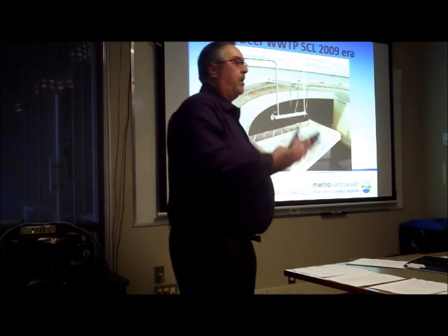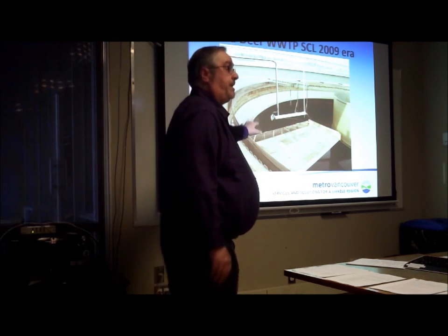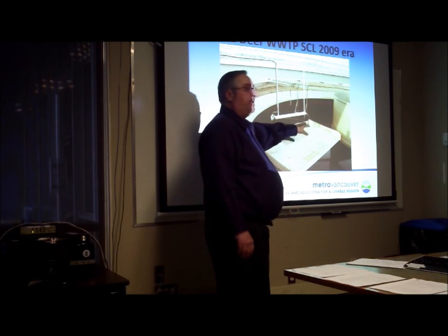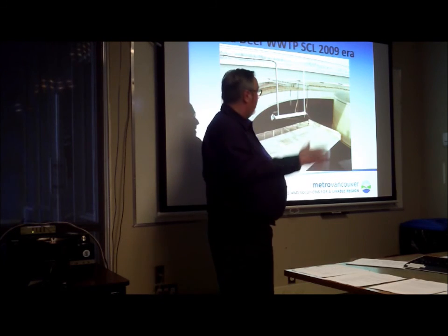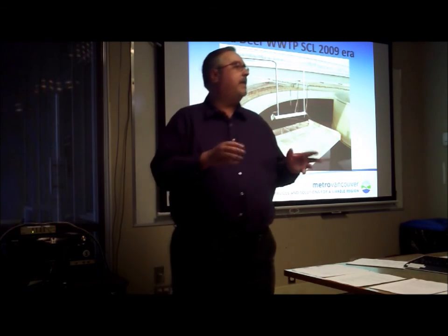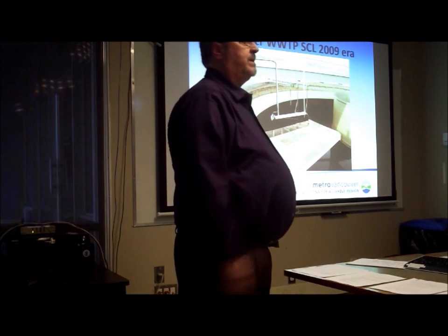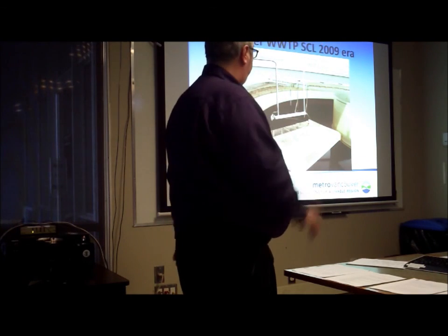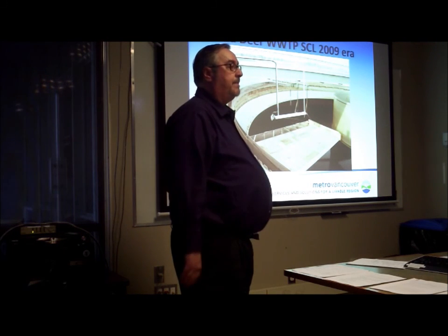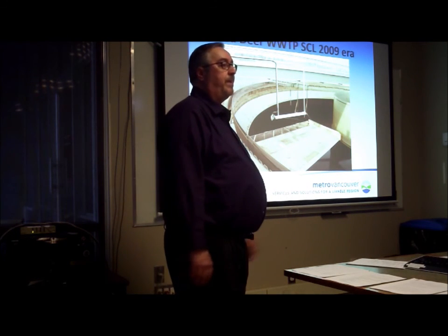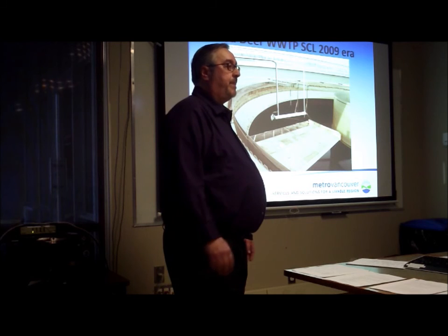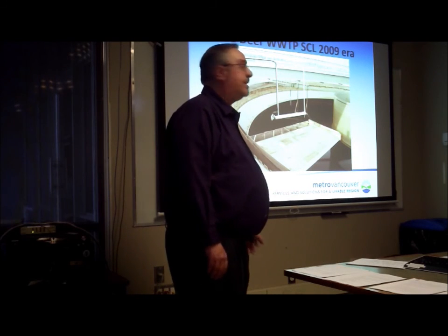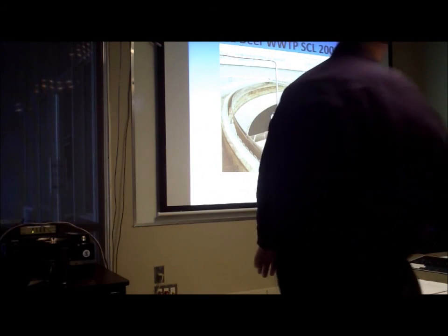Like we battled, you know, Red Deer can get down to 40 below, and when it gets minus 30, minus 40, you can get ice buildup on here. Particularly if you have any kind of solids, foam is really bad. It'll ice up, and then eventually the skimmer arm will get caught on it, and potentially you could break a shear pin. And I have changed shear pins in 30 below at 2 o'clock in the morning, and it's not very much fun.